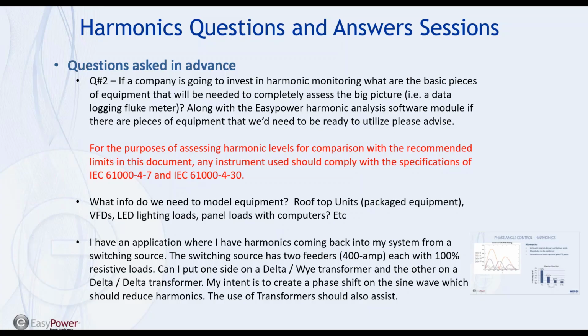So my answer to this question is putting delta Y and delta transformer in makes sense when you have 2 devices that operate at the same phase angle, same load level, and so these devices must be synchronized with one another. If you have 2 drives and they both operate at different speeds, to put one drive on one delta and put the other one on delta Y, if they were operating at different speeds, they are also operating at different phase angles, and the net result is they may still add even when pushed through a delta and a delta Y transformer.